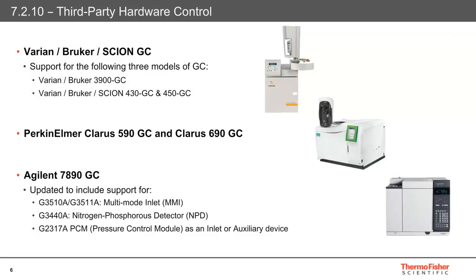For third-party hardware control, we start with support for the Varian, Bruker, and Scion GC versions. Three new models can now be controlled: the 430, 3900, and 450 GCs. The new driver can be found in the Drivers folder on the Chromeleon distributable source media. We can also now control the PerkinElmer Clarus 590 and 690 GCs. Both these configurations are available using the Clarus 580-590 and the 680-690 new driver versions.